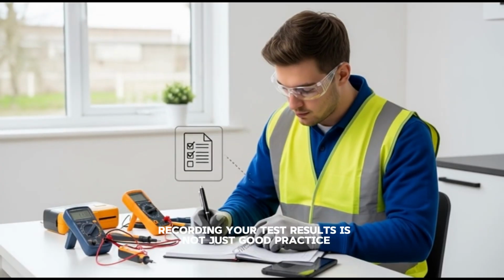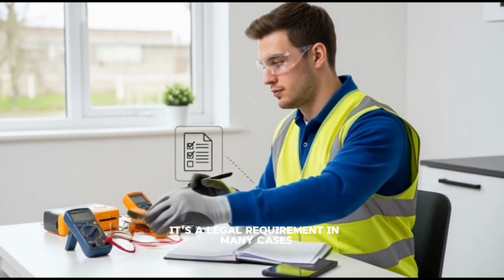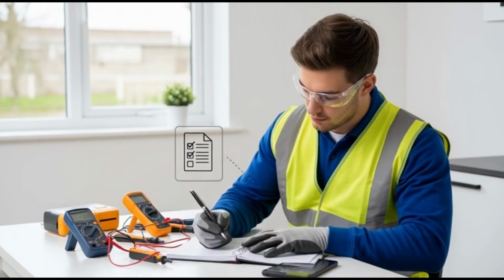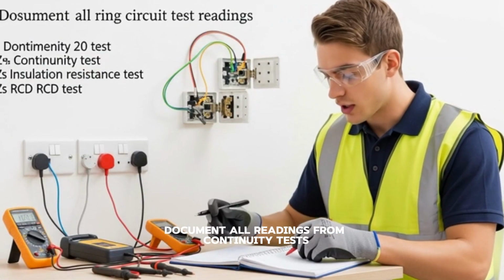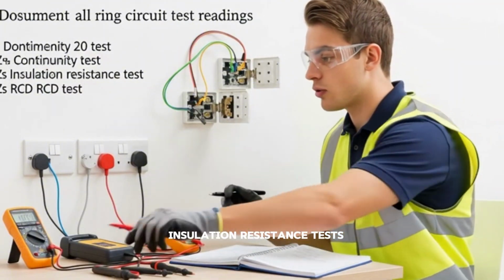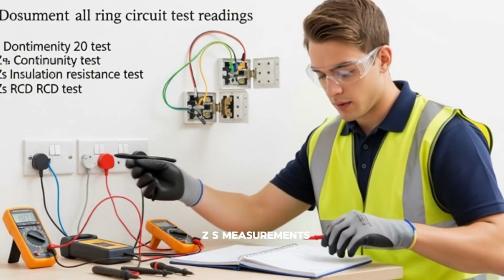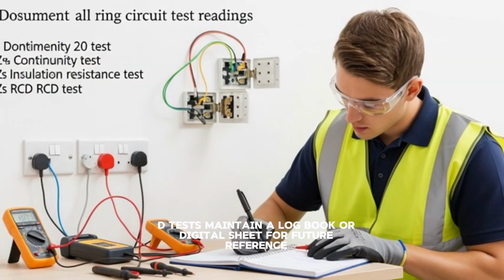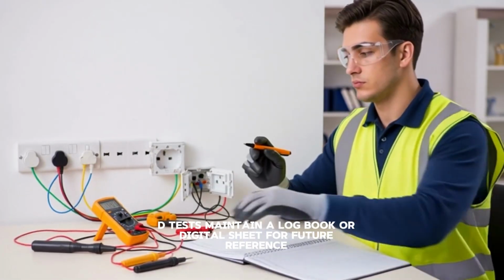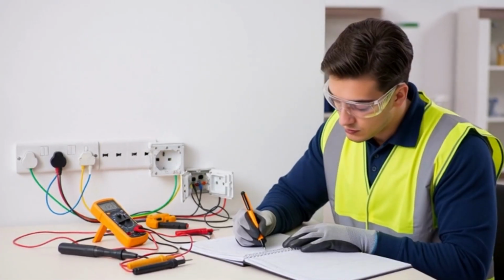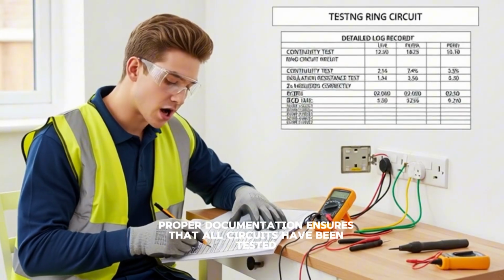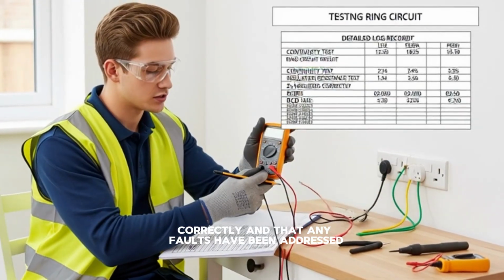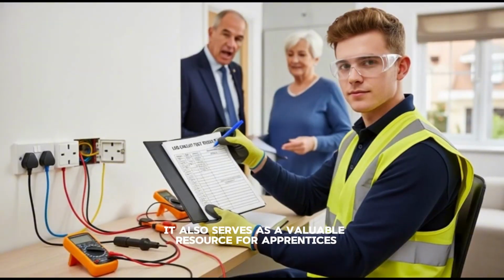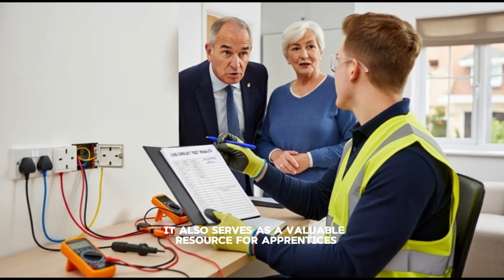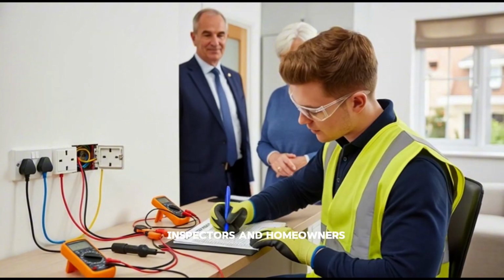Step 7. Document your results. Recording your test results is not just good practice. It's a legal requirement in many cases. Document all readings from continuity tests, insulation resistance tests, Zs measurements, and RCD tests. Maintain a logbook or digital sheet for future reference. Proper documentation ensures that all circuits have been tested correctly and that any faults have been addressed. It also serves as a valuable resource for apprentices, inspectors, and homeowners.